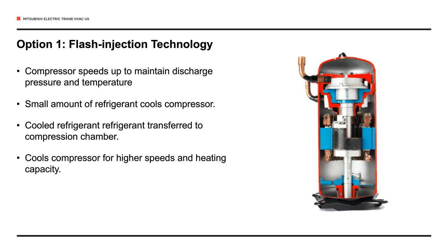If we just overspeed the compressor and didn't do anything else, the heat and friction buildup would cause the compressor to fail. So essentially with flash injection technology, what we're doing is injecting some gas-liquid mixed phase refrigerant into the shell or the dome of the compressor to basically remove that excess heat, so that we can overspeed the compressor without burning it up.